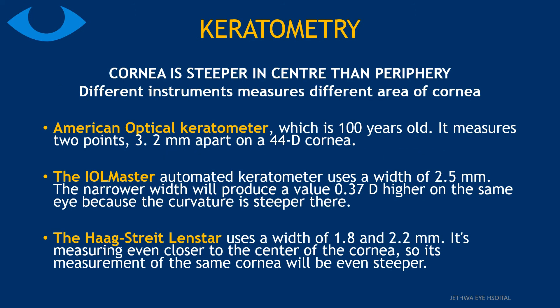We know that the cornea is not a sphere — it is steeper in the center than the periphery. Different instruments measure different areas of the cornea, giving different results. The American optical keratometer, which is 100 years old, measures 2 points 3.2 mm apart on a 44-diopter cornea. The IOLMaster, an automated keratometer, uses a width of 2.5 mm. The narrower width produces a value 0.37 diopter higher on the same eye. The Haag-Streit Lenstar uses a still smaller area of 1.8 to 2.2 mm, measuring closer to the center of the cornea, so its measurement of the same cornea will be even steeper.